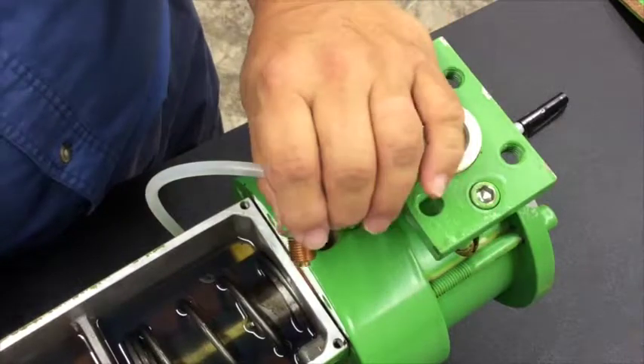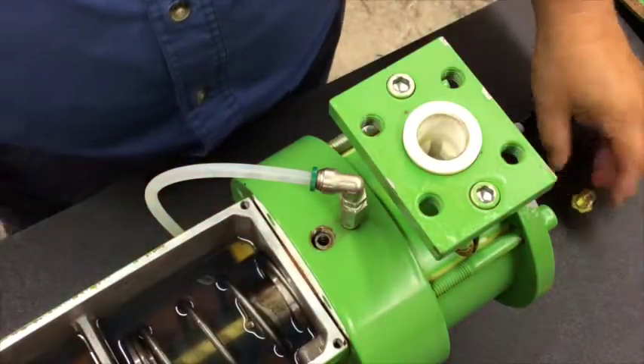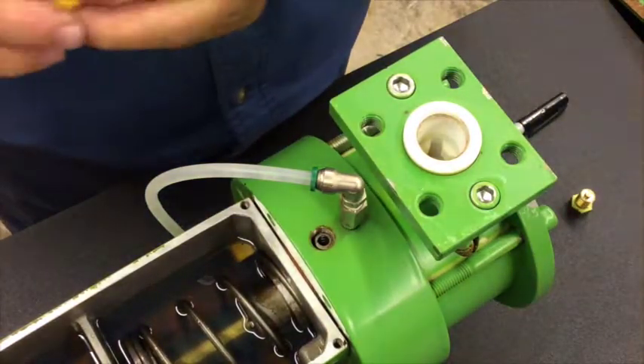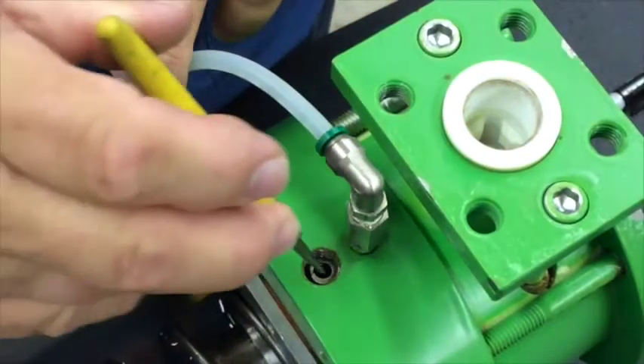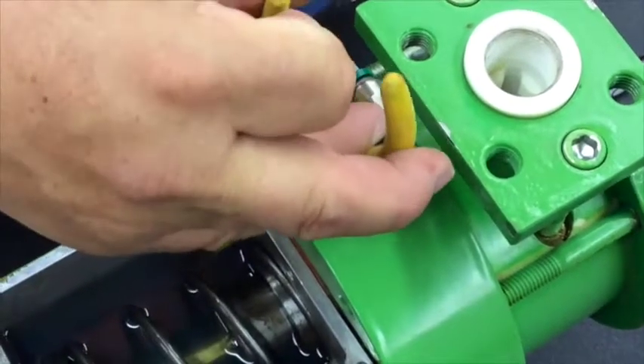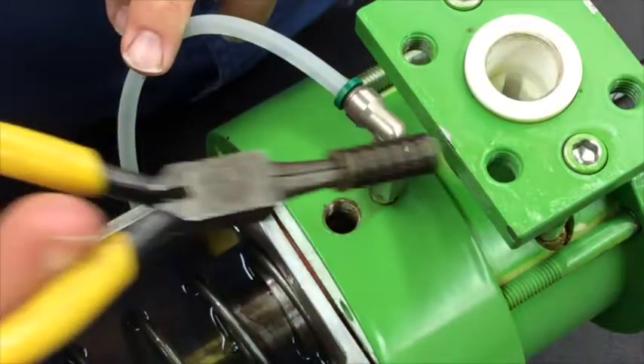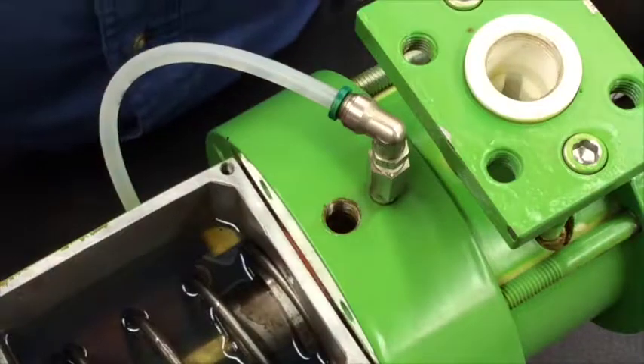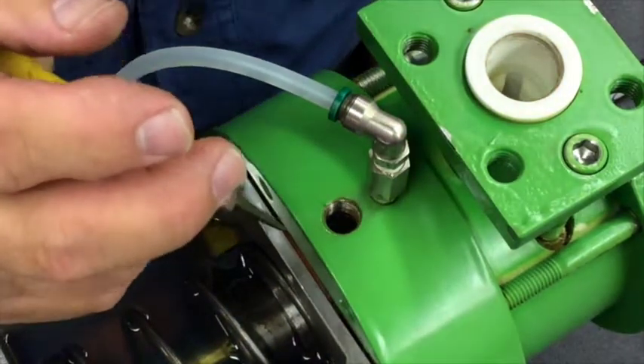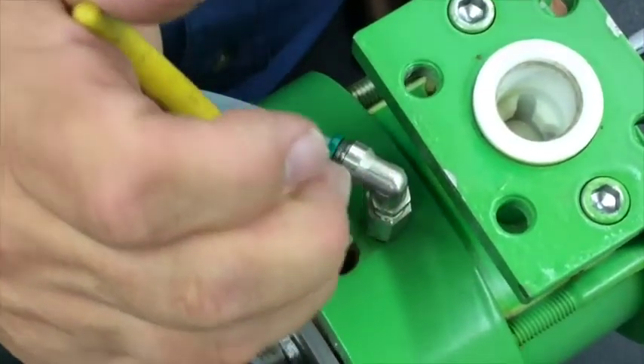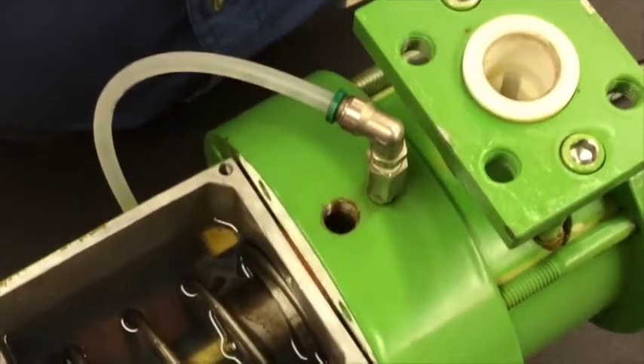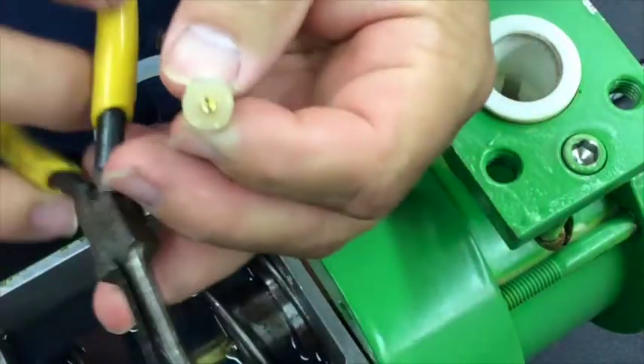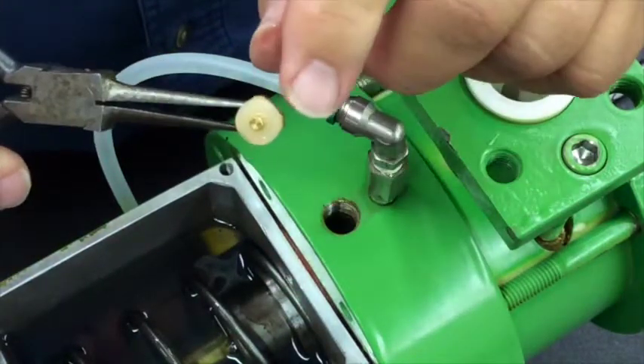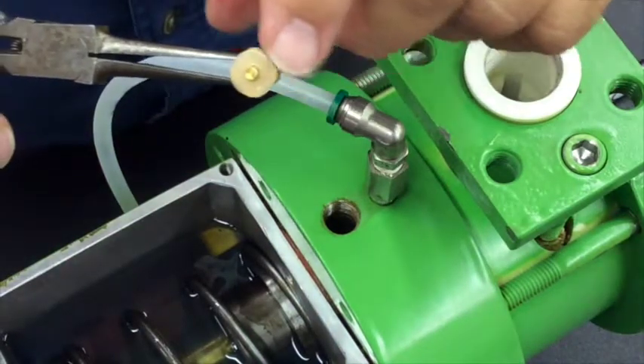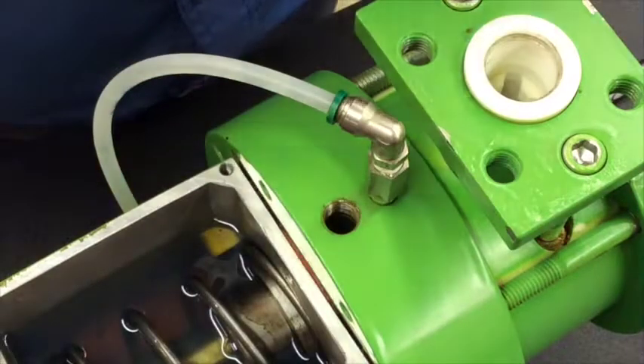Okay, so now I can take the adjustment screw and just set it aside. And if I look down inside here, there's a spring. I'm going to take my needle-nose pliers and press it into the spring and put a little pressure to grab it. And I've now removed the spring. We'll set this aside. And down deep inside here is the seat valve assembly. Yes, and this is what the assembly looks like. I'll put this on here. You can see the plastic disc, which is the seating surface, okay, and then the assembly that supports it. I'll set that aside.